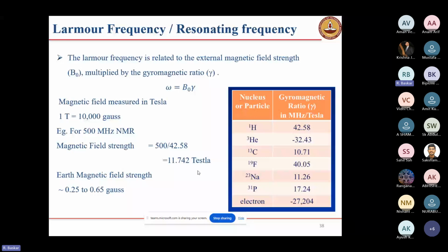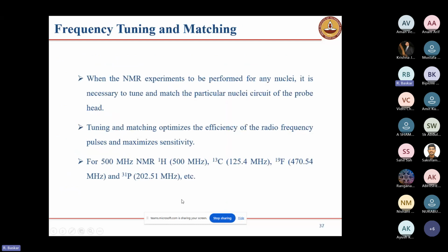In every instrument, for all the experiments, we are not using the same frequency. That is the ATMA, which I explained here. For each individual nucleus, we have to change the frequency. That is called tuning and matching. For example, at 500 megahertz, if you want to do proton, we have to tune the frequency at 500 megahertz. If you want to do carbon, we have to tune the frequency at 125.4. For each individual nucleus, we have to change the frequency. That is called the ATMA or wobbling.